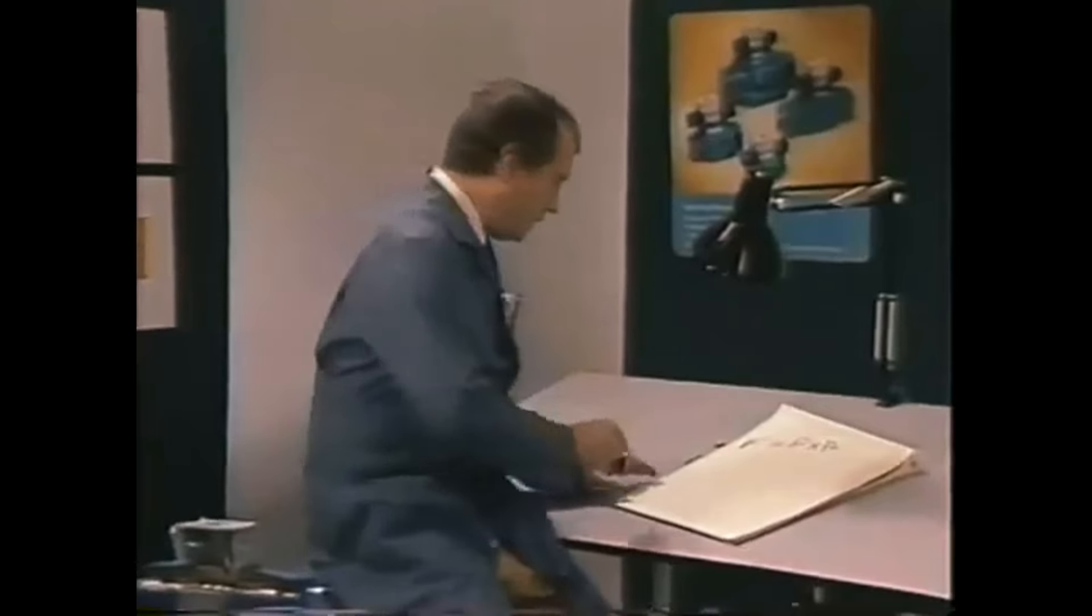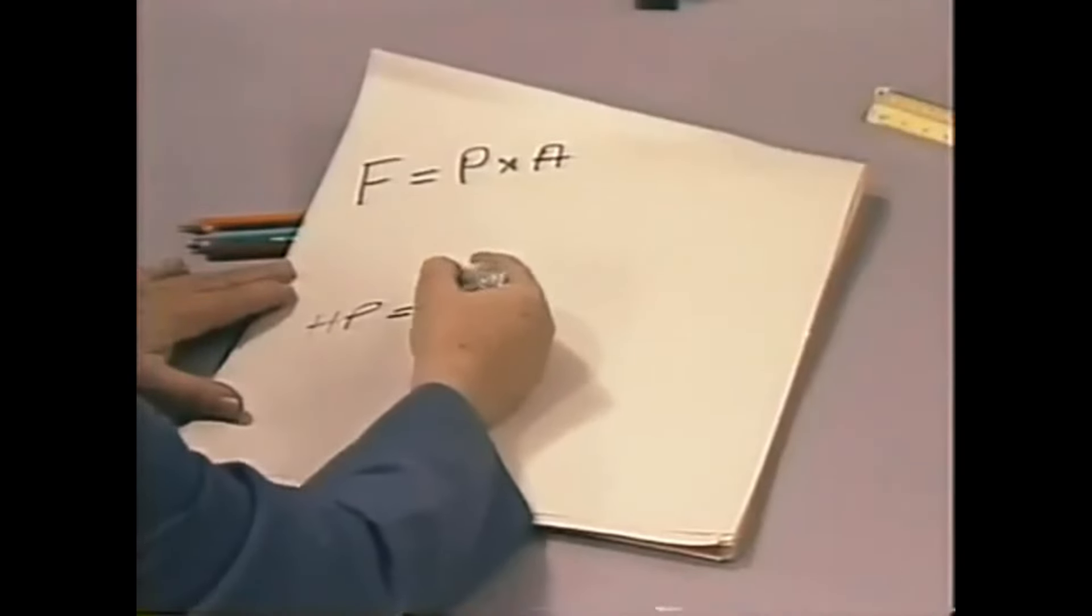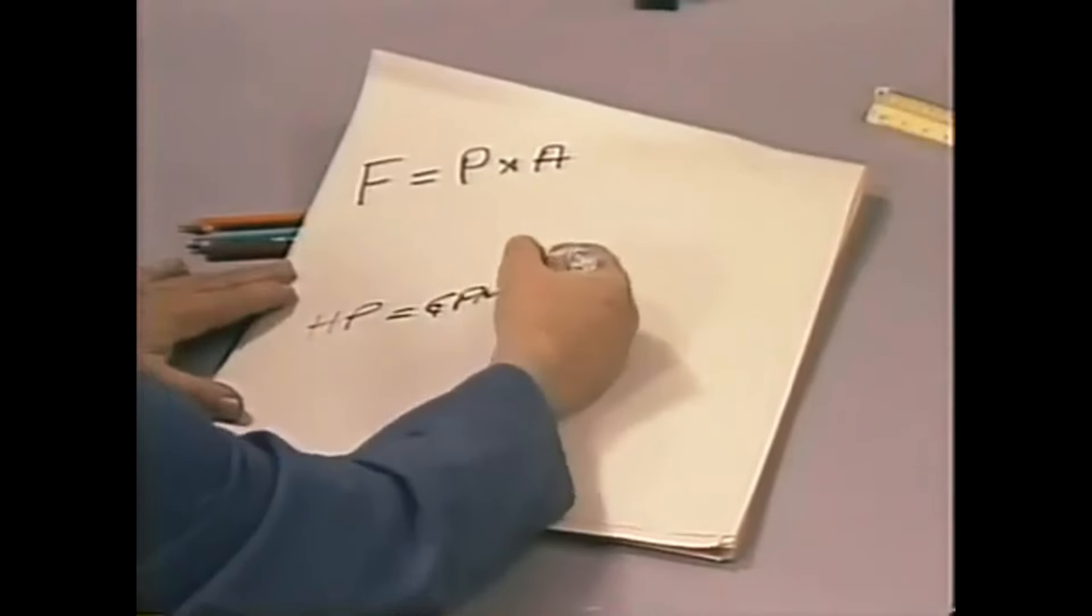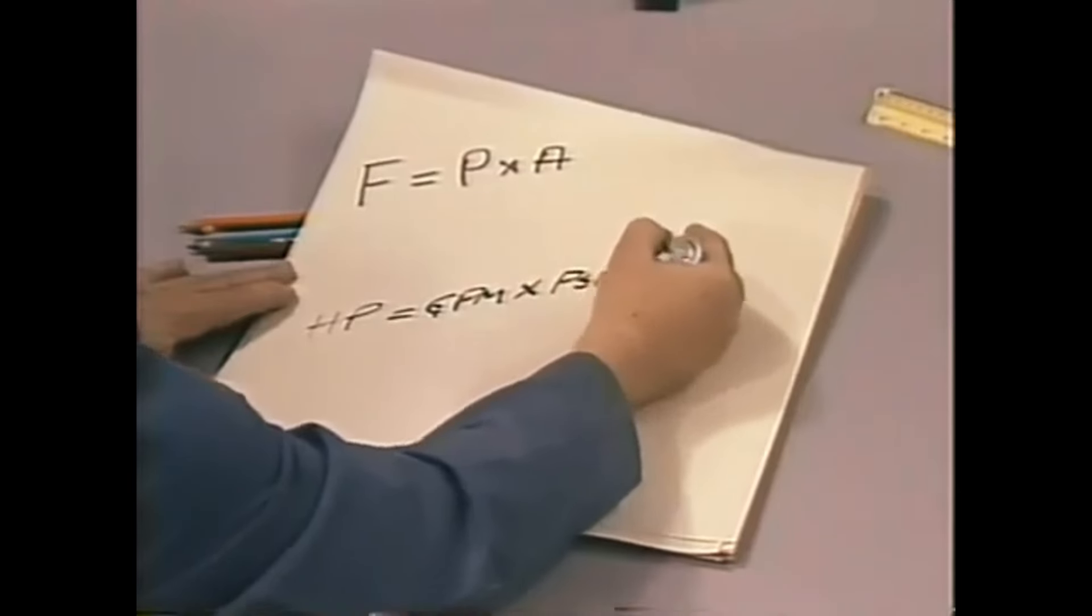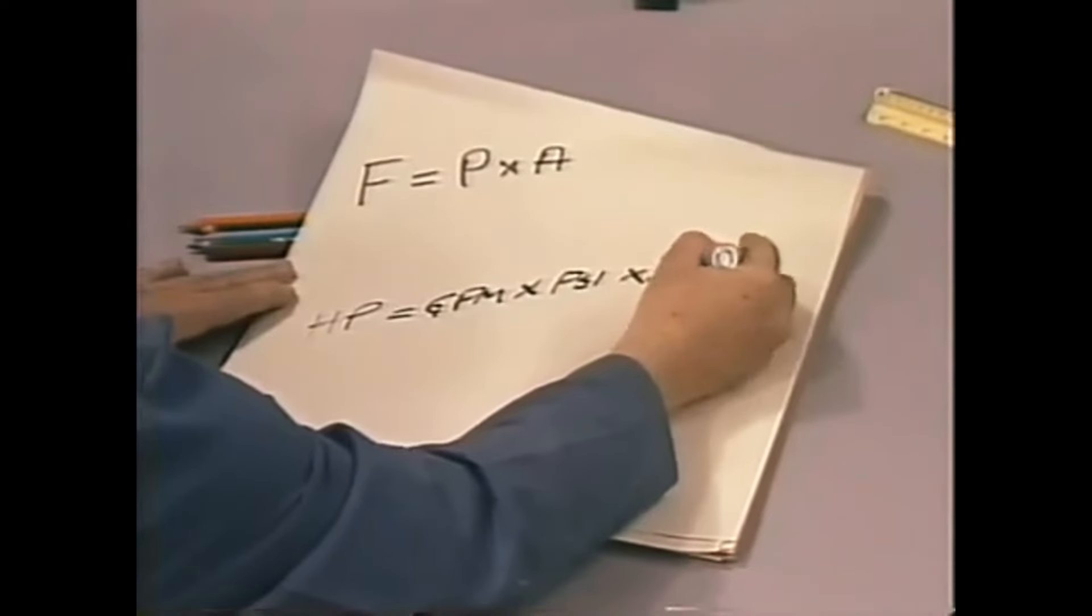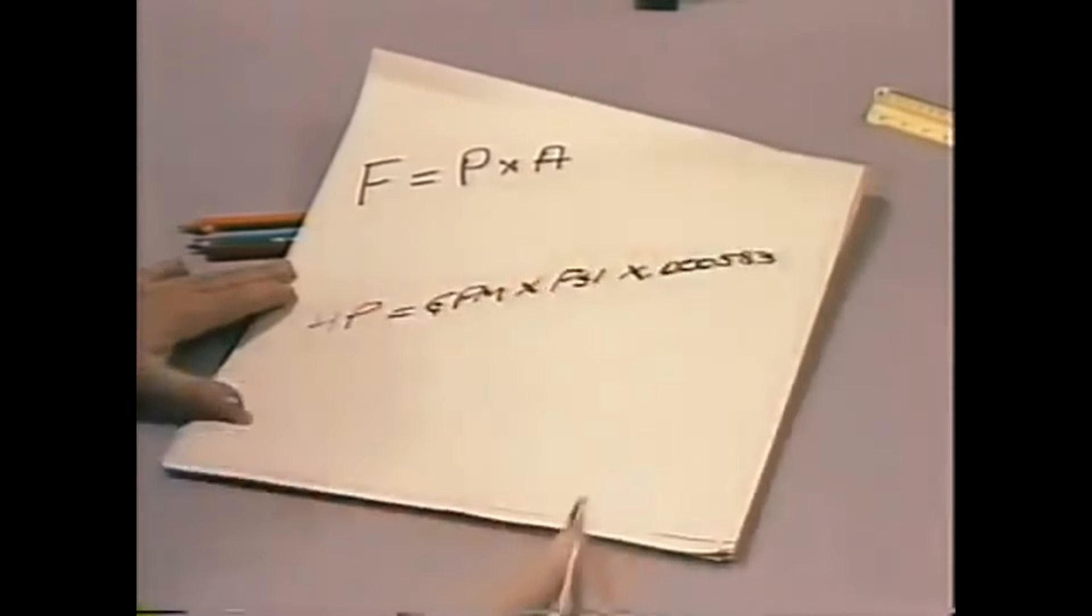Horsepower equals gallons per minute times pounds per square inch times 0.000583. That 0.000583 is a constant. It's the horsepower required to move one gallon per minute at one pound per square inch.